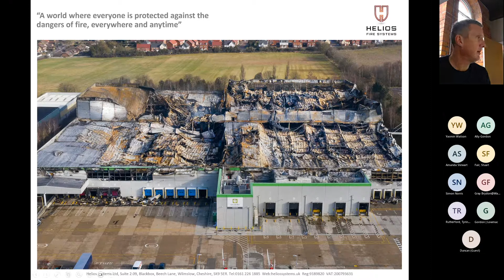This site should have had AMFE. It should have had some form of fire detection inside its control panels. The top floor was all robots, and the control panels for these robots overheated, had some issues and set fire, and they lost the whole building. I think the next slide goes into some details. This was a £120 million site, and it was brought down by 2 controllers inside a control panel which failed. They had no detection inside there, and it went from one cabinet to the next to the next. It caused them huge problems, and obviously they lost the whole building.